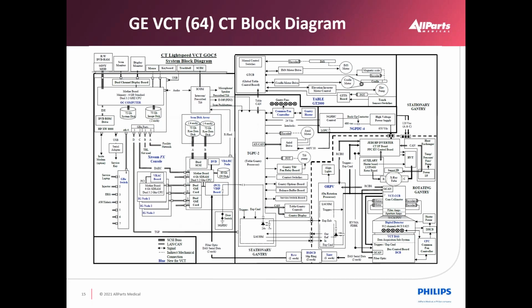So here's a more detailed version of a CT scanner, in this case a GE VCT 64 slice block diagram. As you can tell, the host computer and its processing is all on the left side of the image here. Then we see on the very top of the block on the right is a table control to move the table up and down. And we have touch switches to drive that. Also, we have safety interlocks that keep the table from hitting the gantry. And also, if a patient is interfering with travel, there's a safety switch there, or tape switches we call them, to prevent that travel and injure the patient.